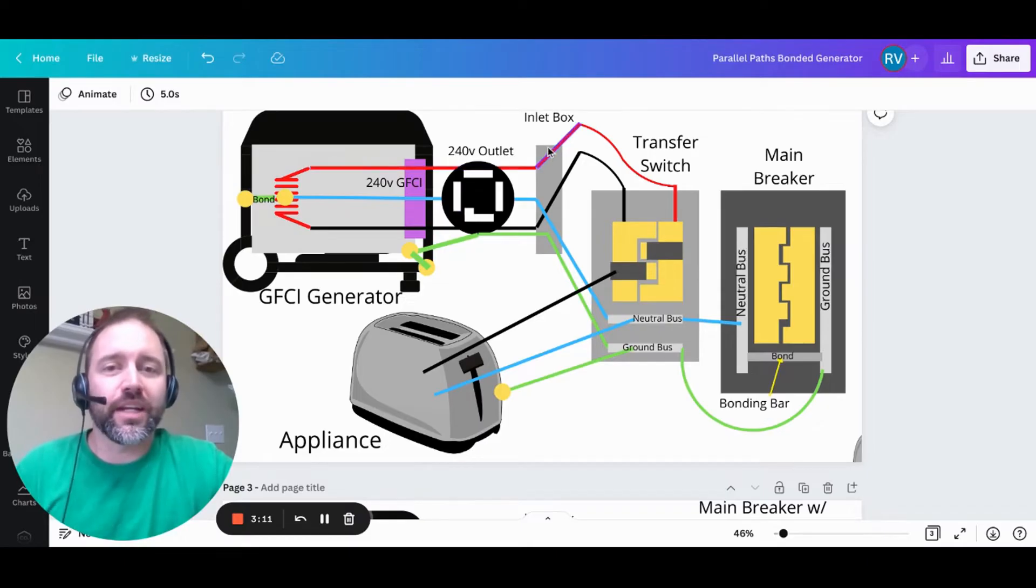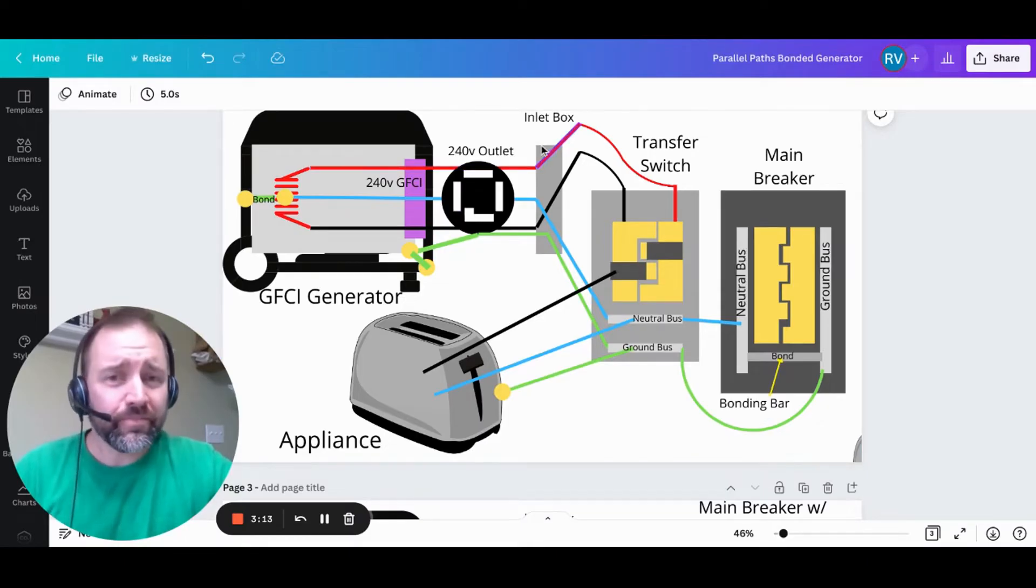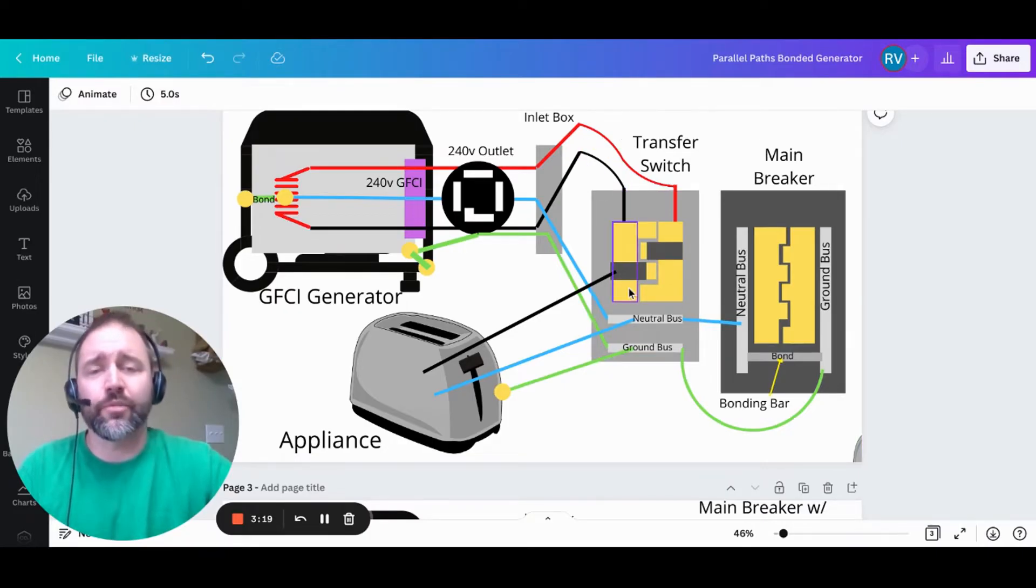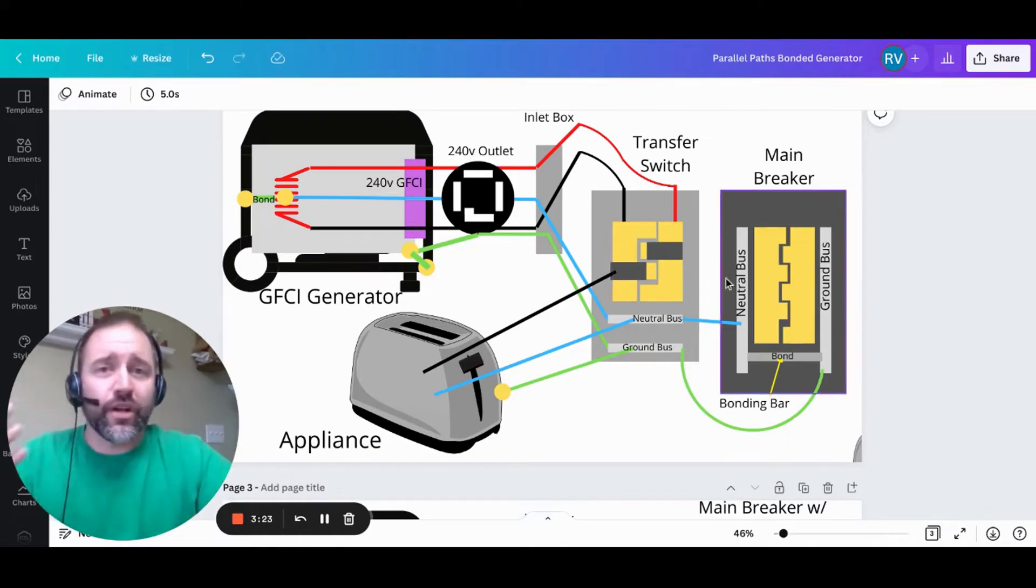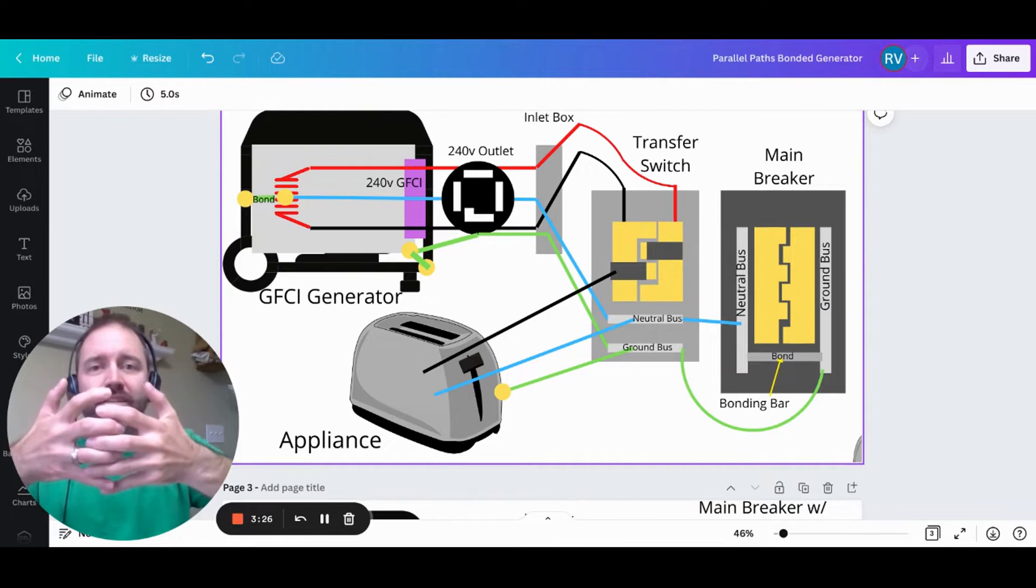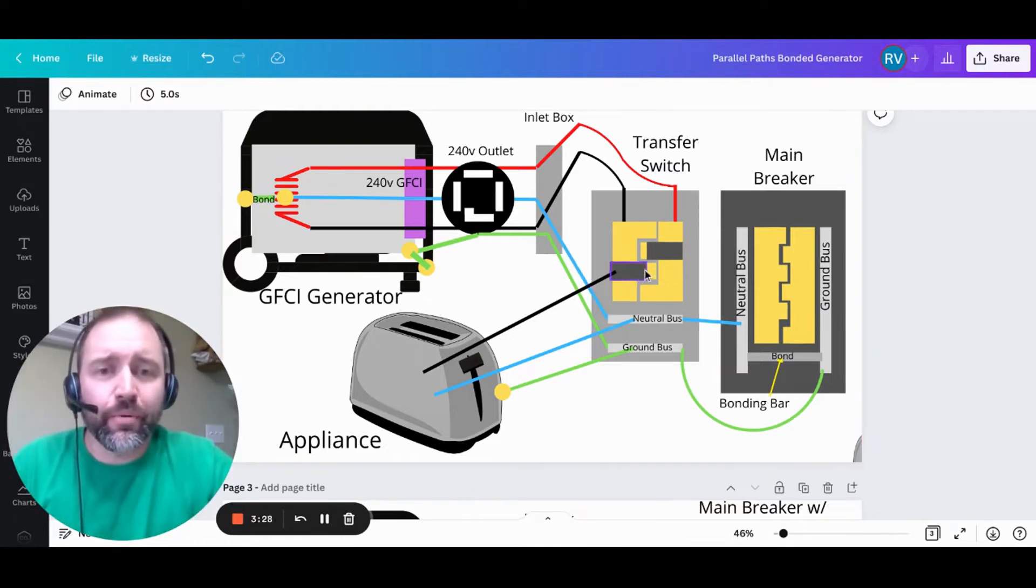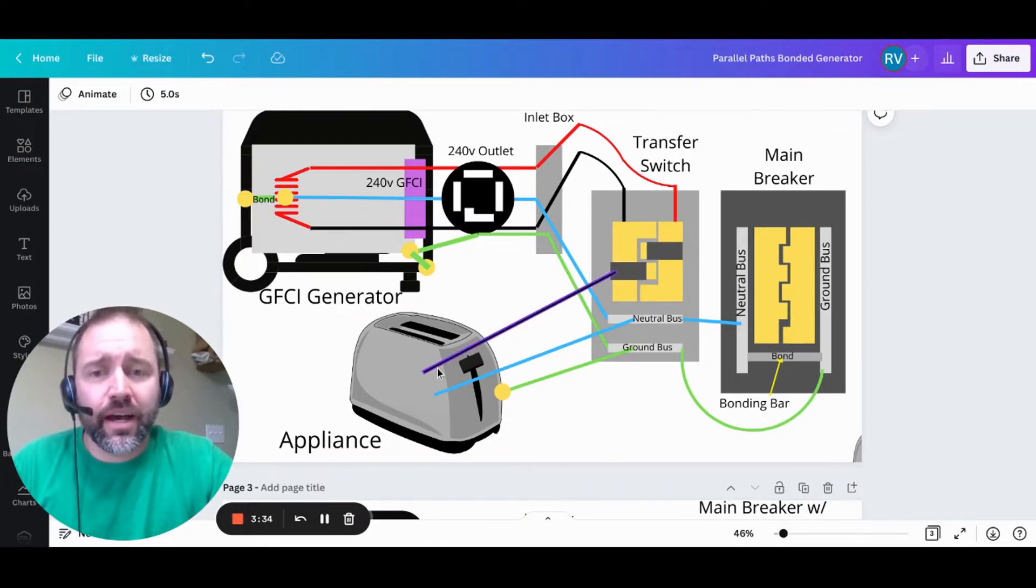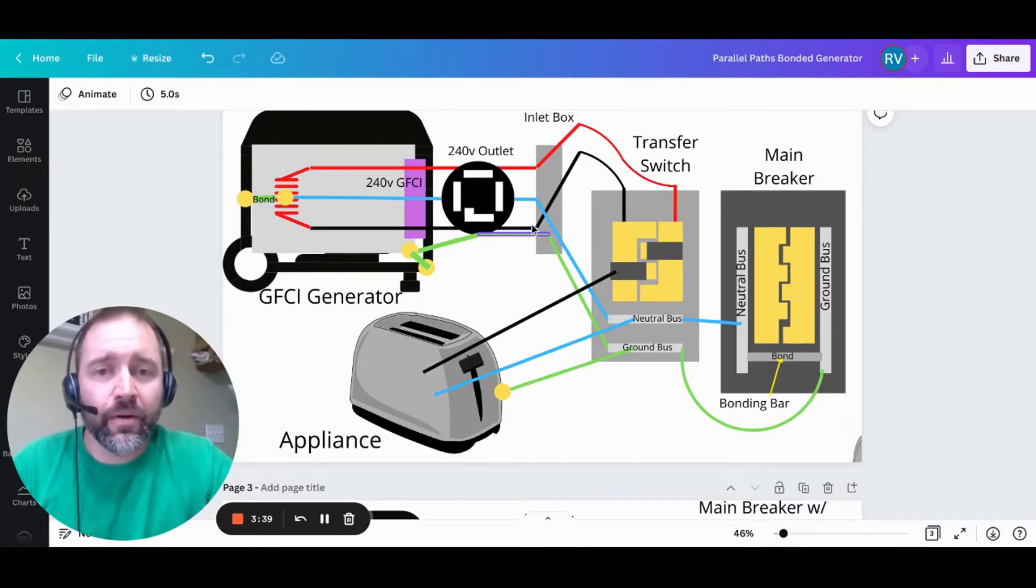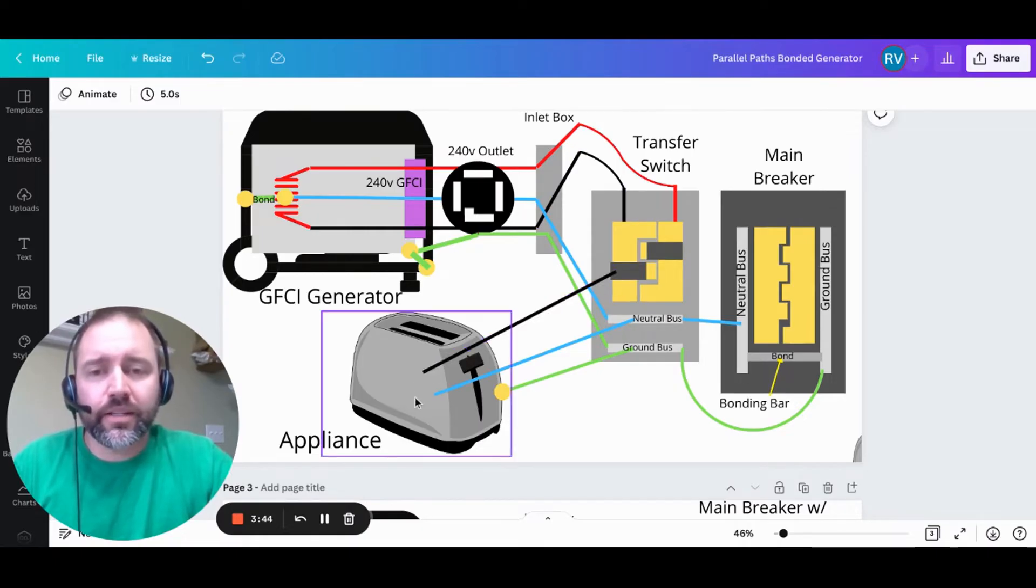The electricity, you plug it into your inlet box here, and you have one hot lead that goes to this bus here, and another one that goes to this bus here. So inside your breaker box, you've got the buses that are kind of like this, and inside your transfer switch is kind of like a mini breaker box with interlocking fingers, and then breakers alternate in between each one. Now, the electricity, we're going to power this appliance on the black one here. So let's pretend this is 120 volts, 7 amps perhaps, coming out, and it will go through here. It will go down here and do work.